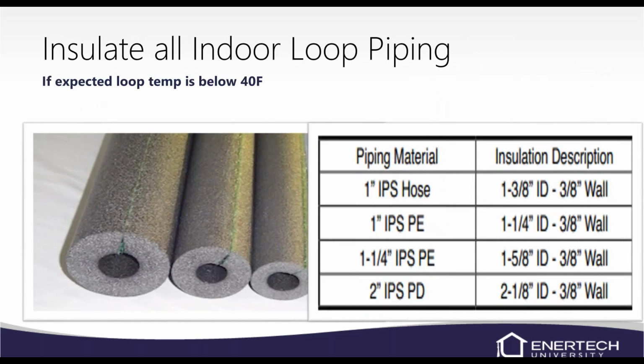Make sure you're insulating all indoor loop piping. Loop temperatures are going to get below 40 degrees more than likely. So just make sure you're insulating your indoor piping or it will sweat.